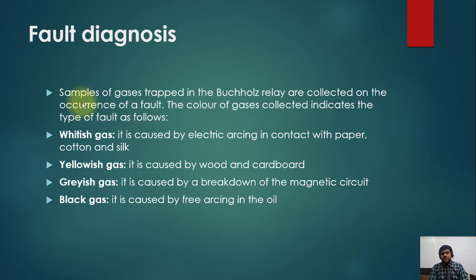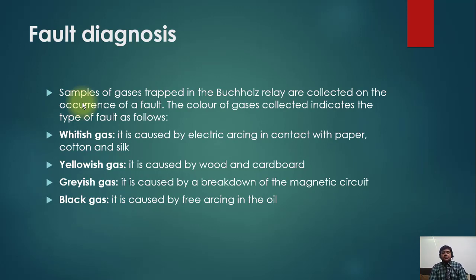To test on-site, you burn the gas and observe the flame color. A whitish flame indicates electric arcing in contact with paper, cotton, or silk. A yellowish gas indicates a fault involving wood or cardboard inside the transformer. A grayish gas indicates breakdown of the magnetic circuit. A black gas indicates free arcing in the oil.